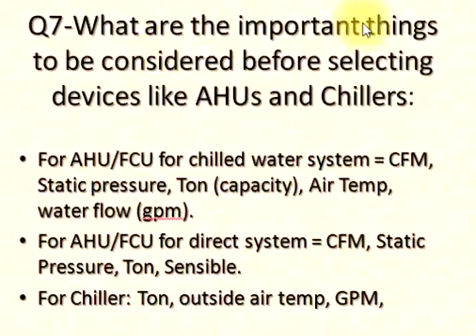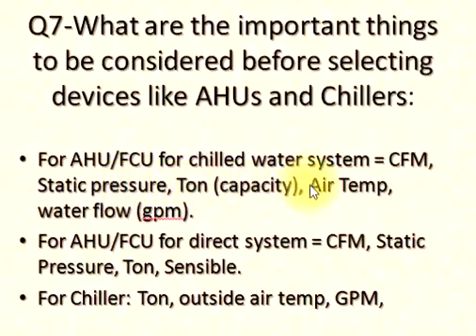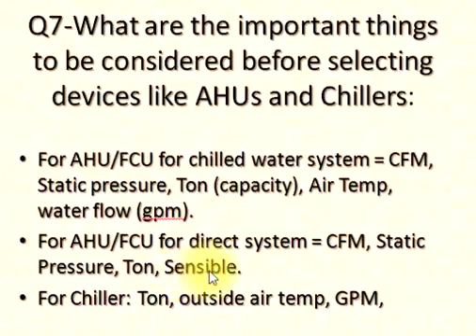Q7: What are the important things to be considered before selecting devices like AHUs and chillers? For AHU/FCU for chilled water system: CFM, static pressure, ton capacity, air temperature, water flow (GPM). For AHU/FCU for direct system: CFM, static pressure, ton, sensible. For chiller: ton, outside air temperature, GPM.